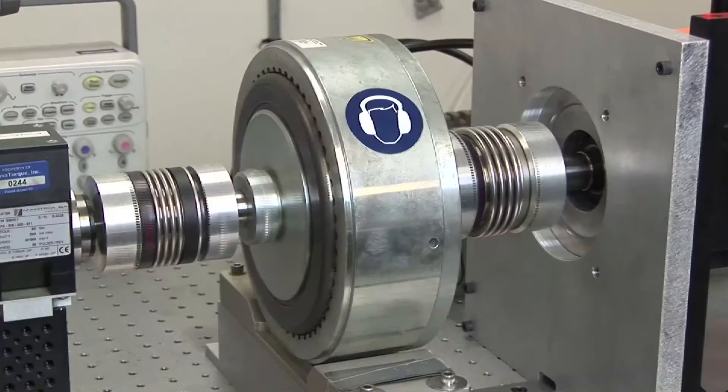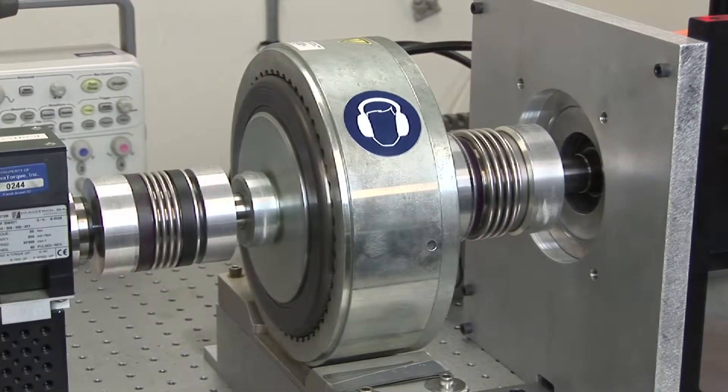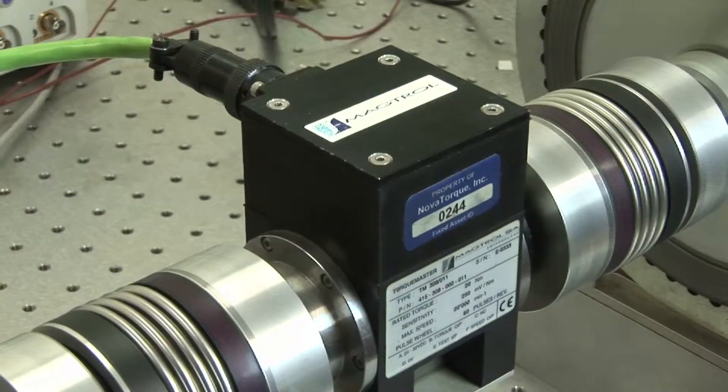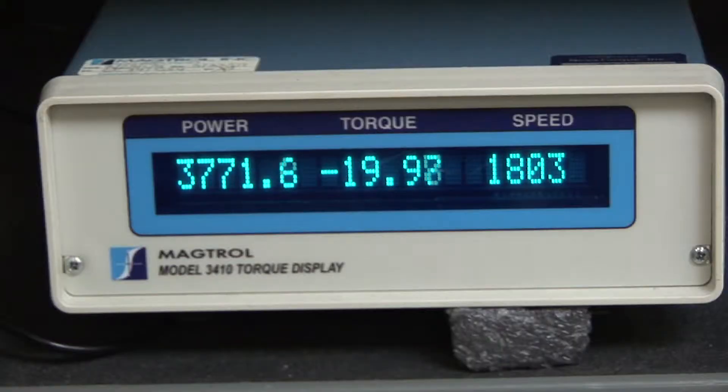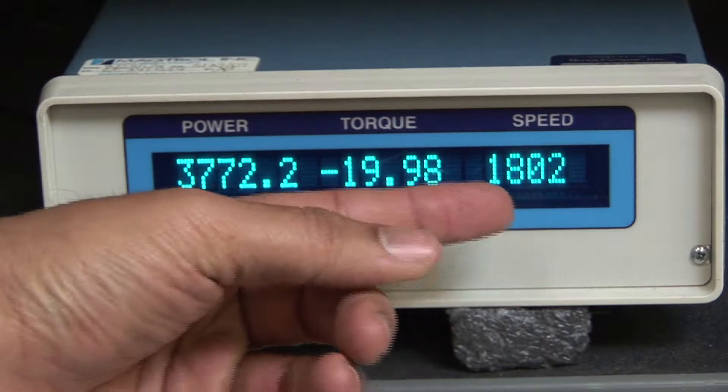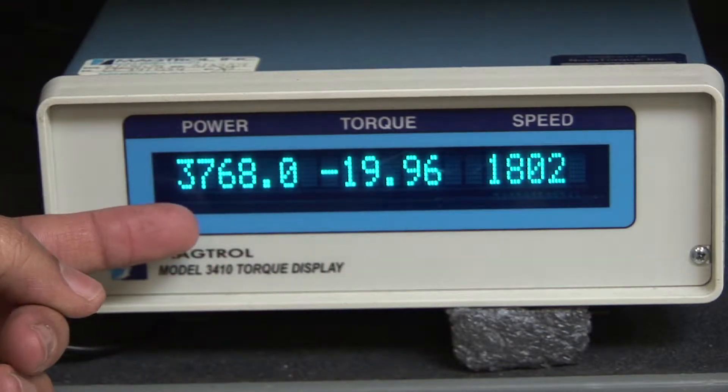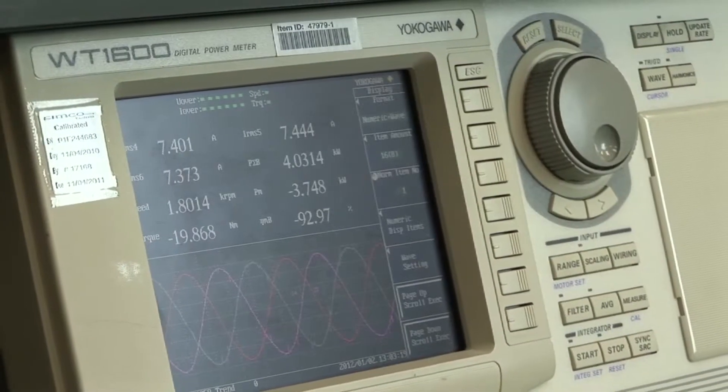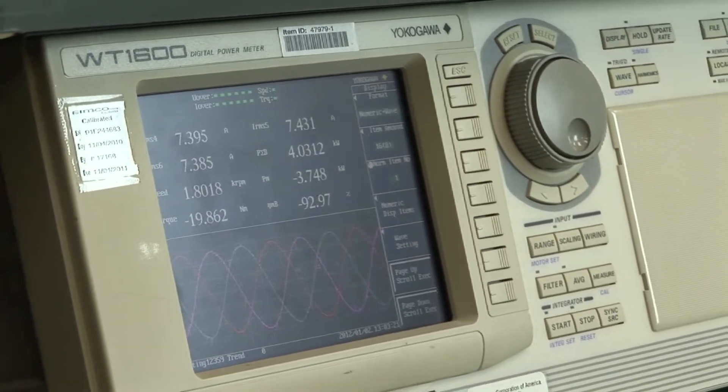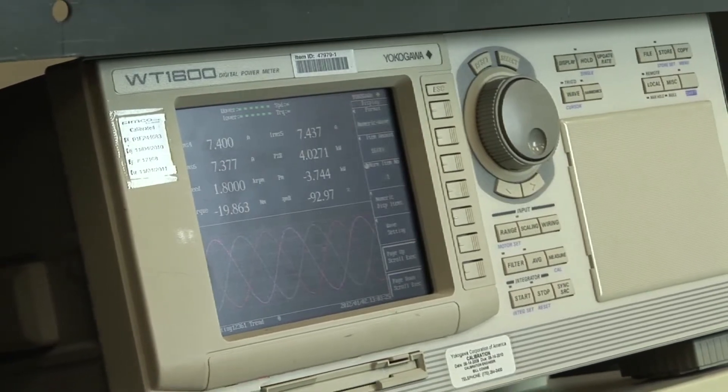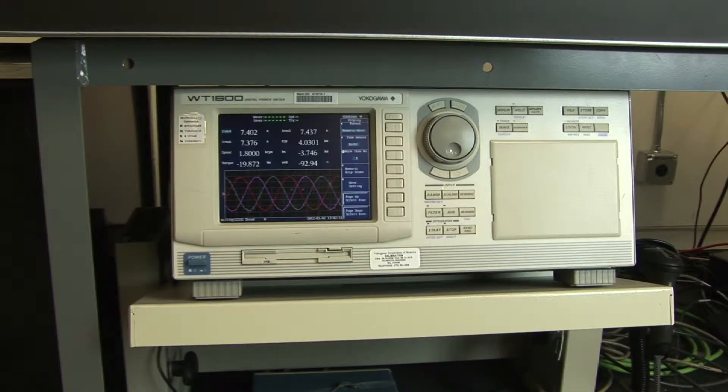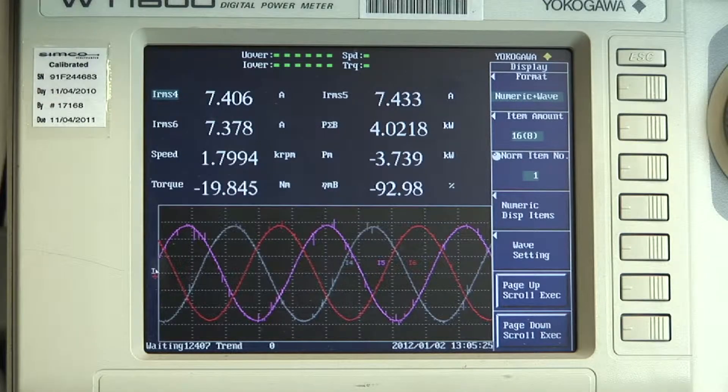The motor is currently operating under load. As the torque transducer measures the torque and speed, we are able to compute the mechanical output power of the motor. The digital power meter measures the voltage and current into the variable frequency drive and the motor. We can therefore measure the power going into the motor and compute both the system and the motor efficiency.